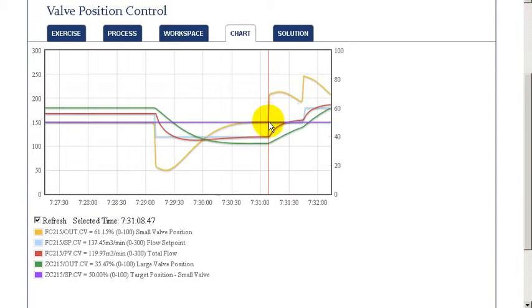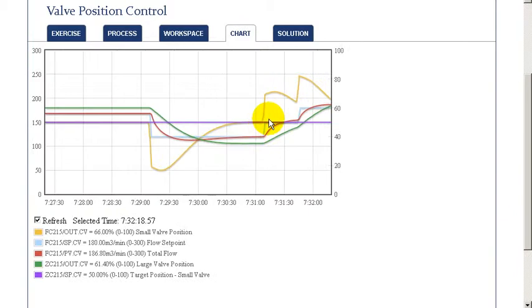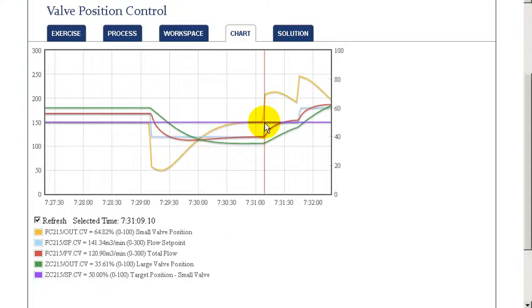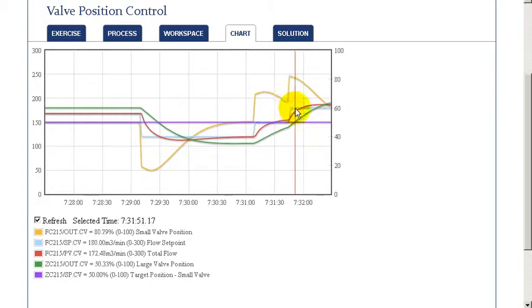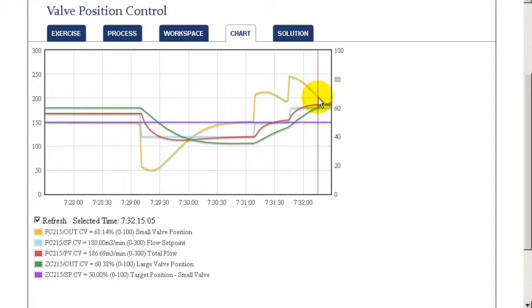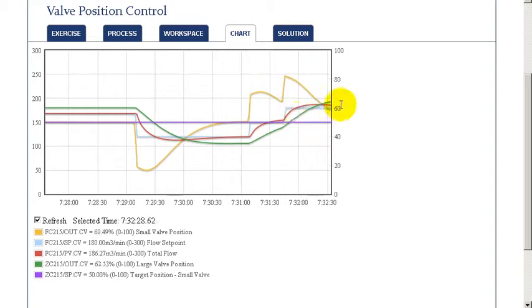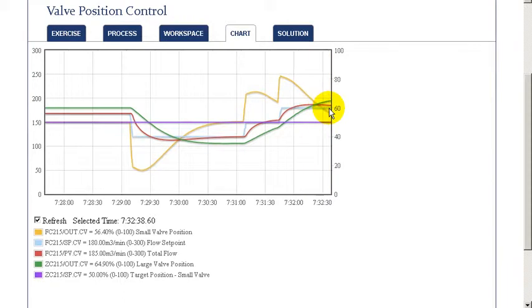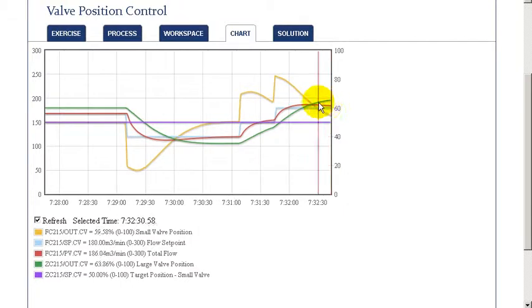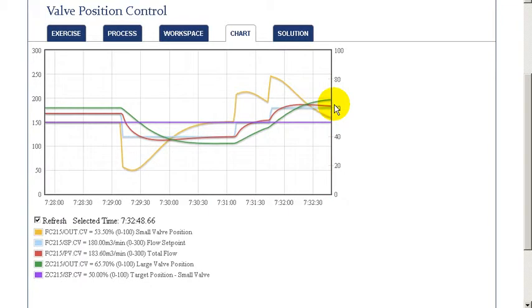As we made each of our changes, we see the smaller valve take action and we see the larger valve very gradually move to keep our smaller valve within its control range. So, the combination of these two valves then allow us to precisely maintain a flow over a very wide range. A wider range than would be achievable by using the small valve by itself.